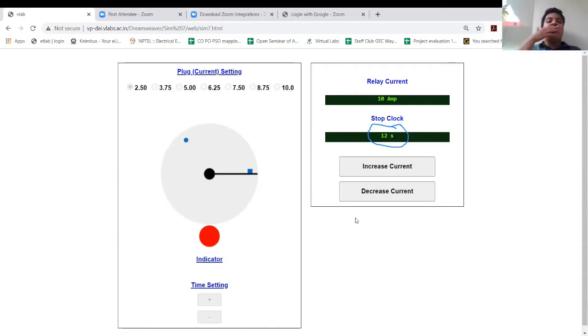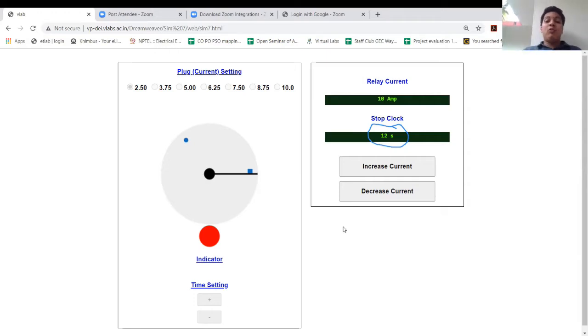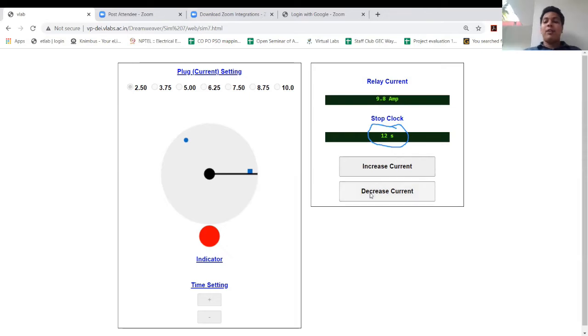So like this, you change the plug setting multiplier from 1.1 to around 6, or relay current from 2.6 to 15 ampere, and note down the operating time. You will take around six readings and for this corresponding TMS you get one observation table. I will be sharing the complete manual of this experiment with you.